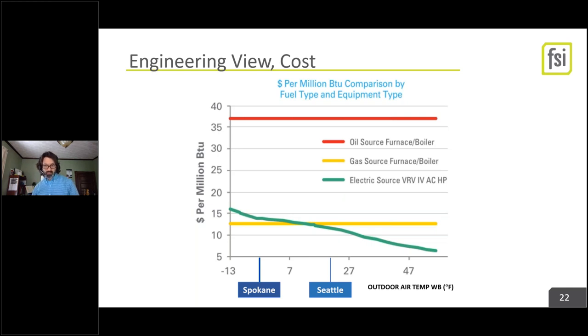So last one, this is the last gospel piece. Heat pumps cost way more than gas. And take this with a grain of salt because it's Daikin specific, but we've also seen this in our energy modeling on various systems, that heat pumps are 3 times more efficient, 2.5 times at those low temps, and conveniently gas costs 3 times more nationwide. I'm sorry, gas costs 3 times less, electric costs 3 times more. So you end up at basically a wash on energy costs. And for the Pacific Northwest with our hella cheap electricity, you can actually end up slightly ahead. Add in the savings of not pulling in a gas line, and heat pumps start looking pretty good.